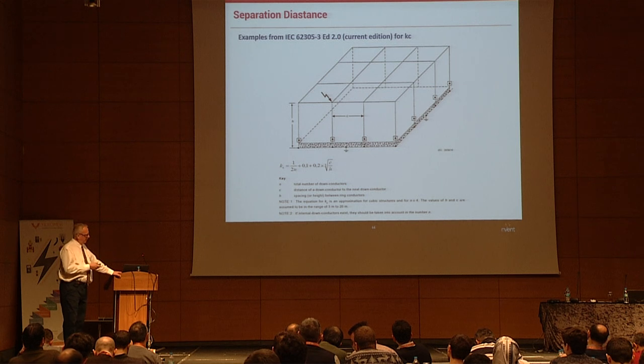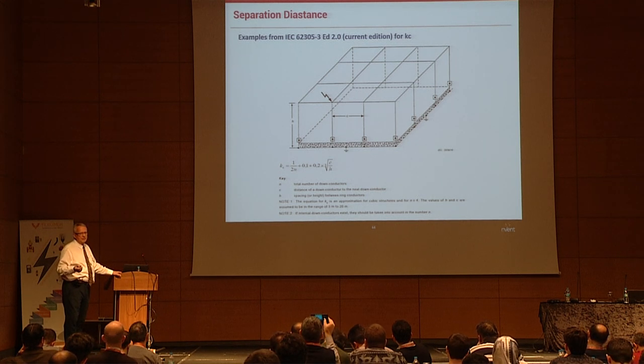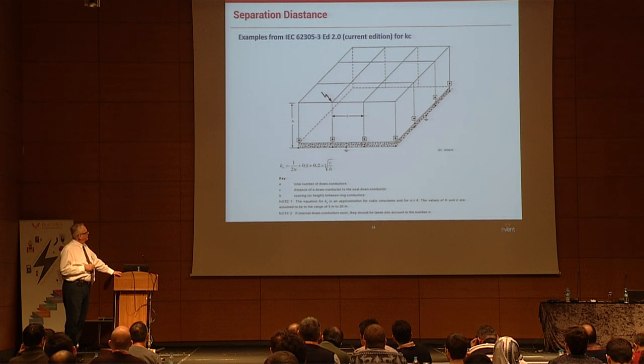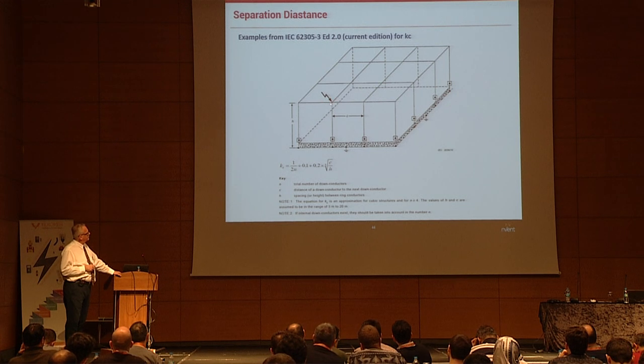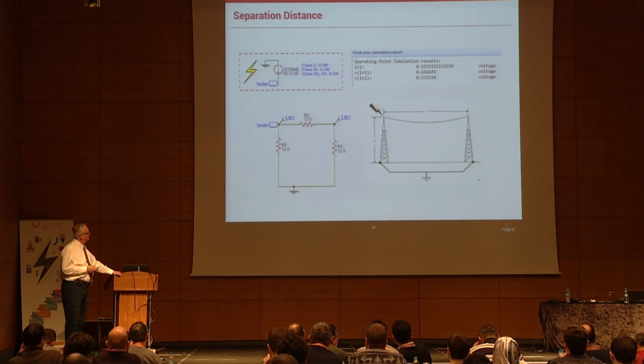There's a special case common for the British standard — they use a mesh over the building with a different formula, and it also matters where the strike is. You can also use software that models the system using equivalent circuits of resistor networks, assigning values by measuring the resistance of the wire, then calculating. The grounding is the source, the strike is the striking point, allowing full calculation.